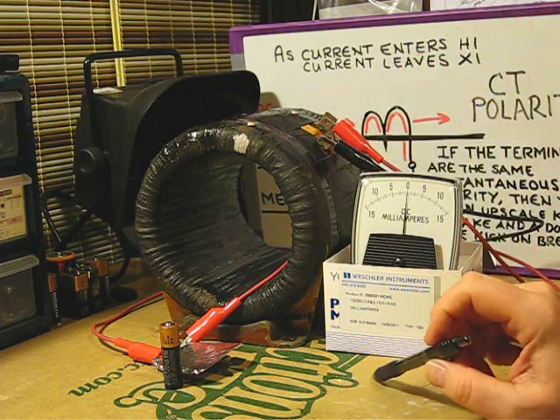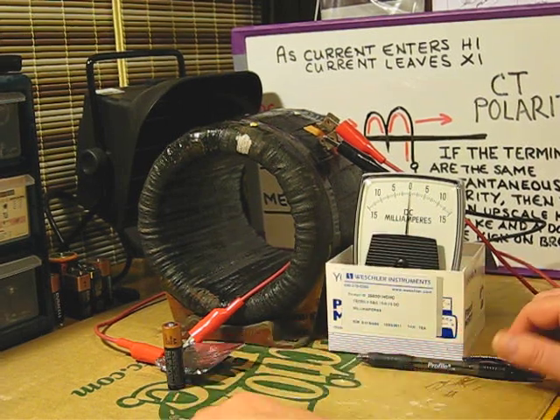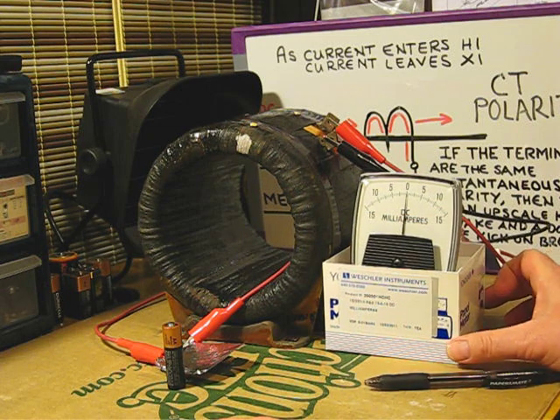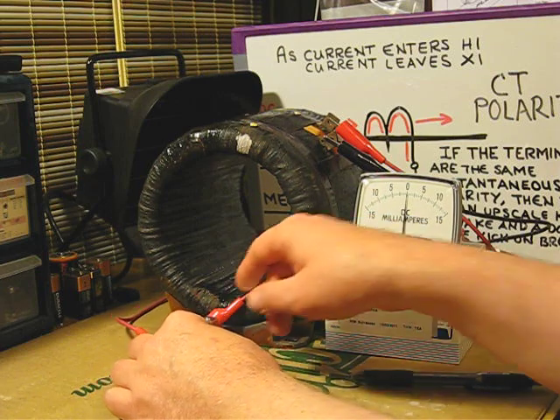You'll notice that we're going to inject into the primary side, which will give us a scaled down reading. This is safer for personnel and equipment than going from the low side to what would be the high side here.